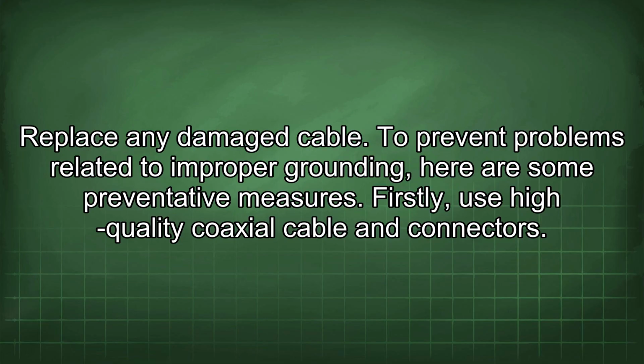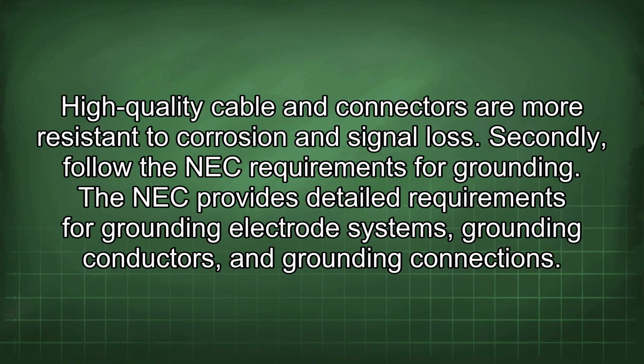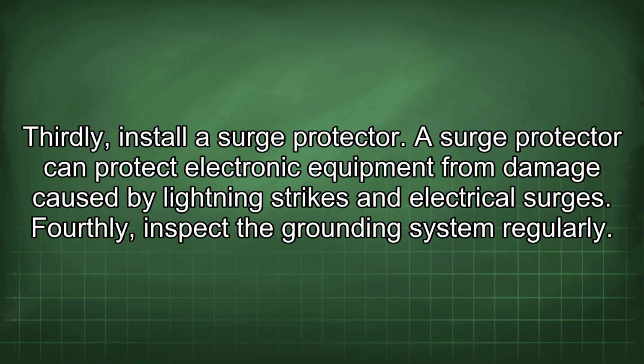Firstly, use high-quality coaxial cable and connectors. High-quality cable and connectors are more resistant to corrosion and signal loss. Secondly, follow the NEC requirements for grounding. The NEC provides detailed requirements for grounding electrode systems, grounding conductors, and grounding connections. Thirdly, install a surge protector. A surge protector can protect electronic equipment from damage caused by lightning strikes and electrical surges.